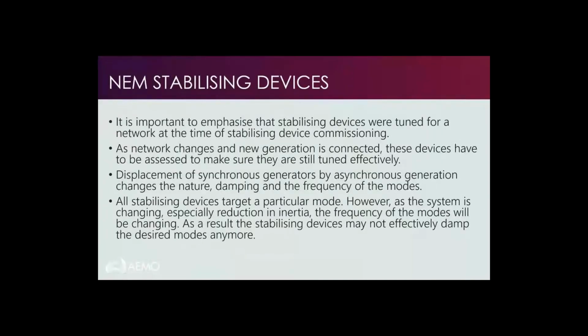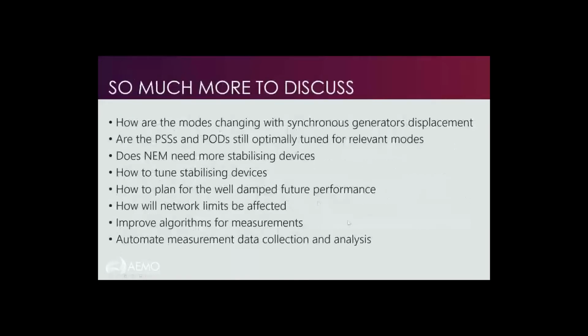One thing to emphasize is that when stabilizing devices were tuned, they were tuned for the network at the time of stabilizing device commissioning. So for the network and generation at that time. As the network changes and new generation is connected, these devices have to be assessed again continually to make sure they are still tuned effectively. Especially with the displacement of synchronous generators by asynchronous generation, that will change, and it has changed the nature, damping, and the frequency of the modes. So we definitely have to continually assess small signal stability to see that our stabilizing devices are still targeting the modes we want to target.